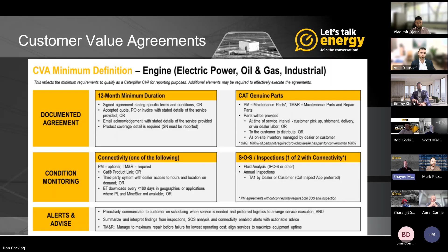Along with all of the standard services, we also offer other services such as vibration testing on your CAT equipment. With proper baseline, consistent vibration testing, it's an easy way to spot if something's not working quite right. With elevated readings on certain orders, a good interpreter can predict which component of your engine or generator should be looked at, without much invasive troubleshooting.